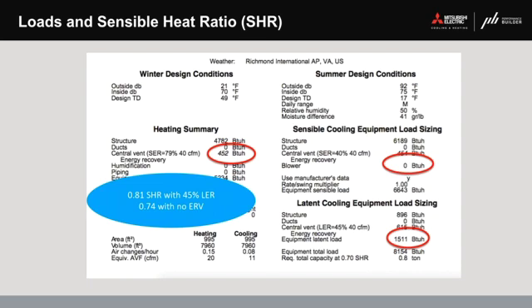And again, because our building envelopes are performing better and we're not having the conduction losses that we had prior. But what's not changing are what we call our latent loads. So latent load is just another way to say moisture load or humidity load. So if we consider a way to describe what has changed about spaces as our codes have increased and building performance has improved, the sensible load has gone down. The latent load has stayed the same or even increased due to ventilation requirements.